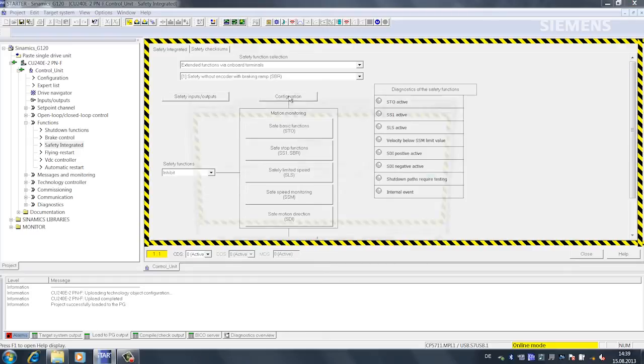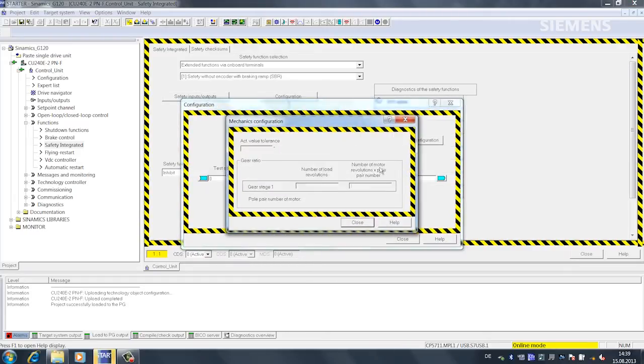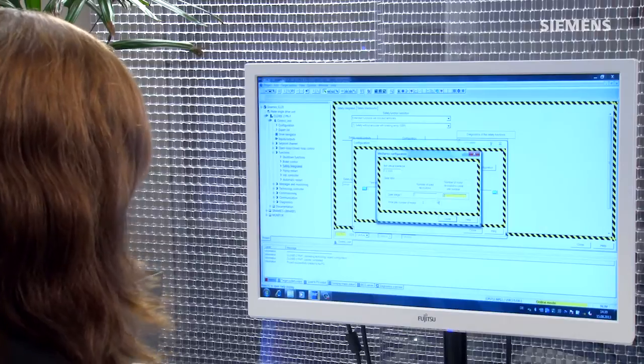Now we set up the gear settings. Since we have an encoderless safety function, we must enter the number of pole pairs into the speed ratio.